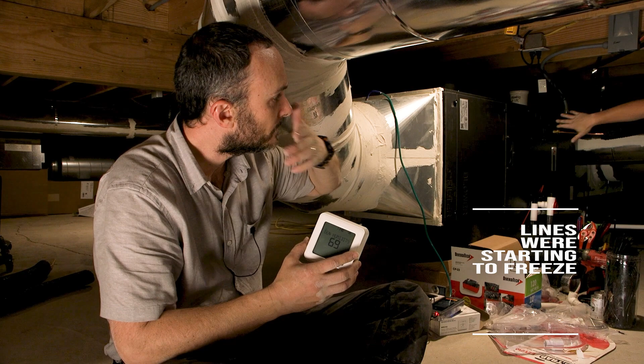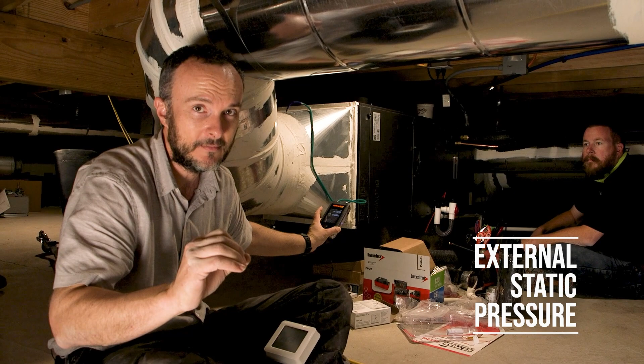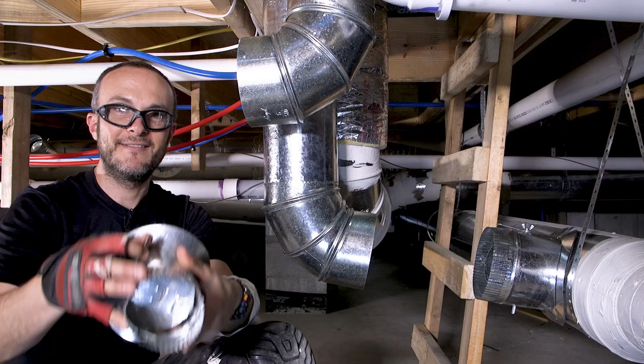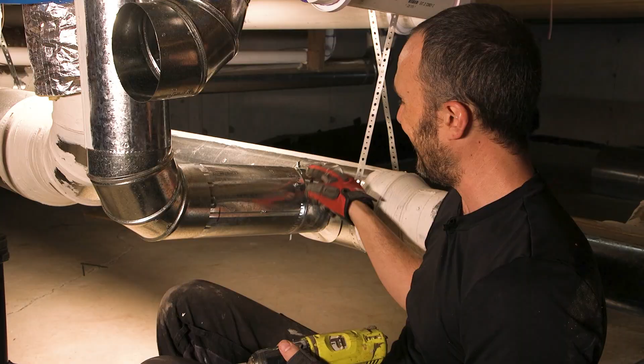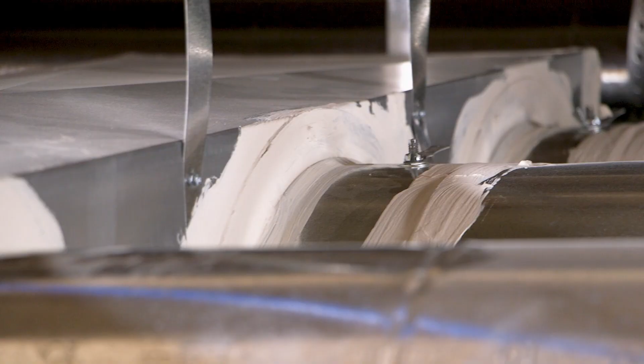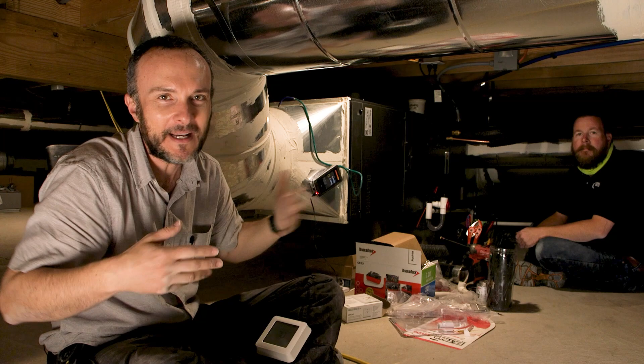Brent, you found out first that our lines were starting to freeze up. We started to have frost build up on our refrigerant lines, so that was saying hey, something's going on. Specifically, that's a key indicator that the air is not moving like it should. So we first tested the pressure—0.03, which in HVAC speak is basically zero. That means no air is moving through this, there's no pressure. This system has dampers all over it, because I like to control and tune things. We got over to the two main trunk lines, and both of those were totally shut. At some point, somebody, probably me, had just brushed past them and closed them.